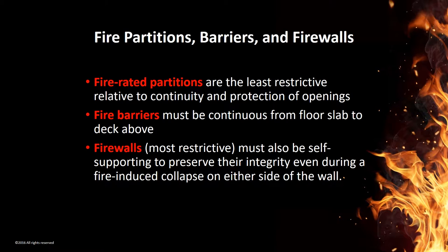The most restrictive and most demanding type of fire resistance rated wall is the fire wall. In some cases it's also known as a party wall or a separation wall. This must be self-supporting throughout all of the stories of the building and it must maintain its integrity during a fire-induced collapse on either side of the wall. This is a special unique case of a fire resistance wall with extra design requirements in terms of collapse prevention and self-supporting stability in the code.